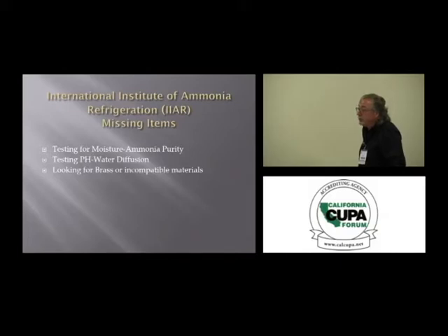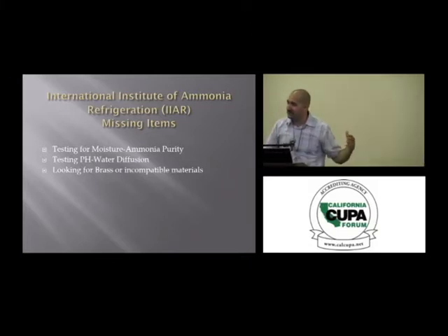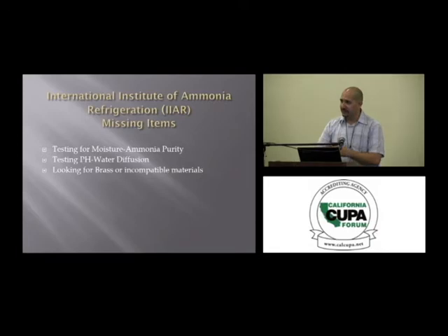But there is no real way. I wish we could make our systems out of glass so we could see inside. You're going to have higher operating costs too. Absolutely. Well, this particular system, what we ended up doing is we drained the entire system, sent the ammonia back, they were planning on using it as fertilizer, which ammonia is fertilizer. We ended up draining the system and we ran different size vacuum pumps for 3 weeks to pull all the moisture out as best we could. Then we put anhydrous ammonia in it.